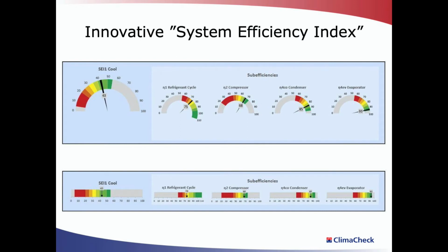For many years we've been using COP, coefficient of performance, as a benchmark for measuring the efficiency of a system. So a COP of 3:1 is applicable to a system that has 90 kilowatts of cooling divided by 30 kilowatts of power input. However, COP moves with the cooling capacity change in response to the load and also with ambient conditions. So COP is moving up and down across the day and across the week and months like a fiddler's elbow, and is not really much use in the field.